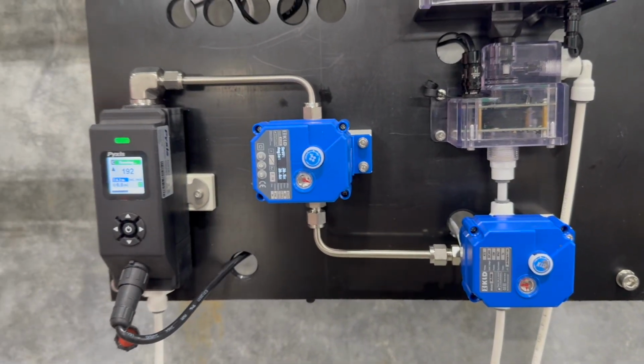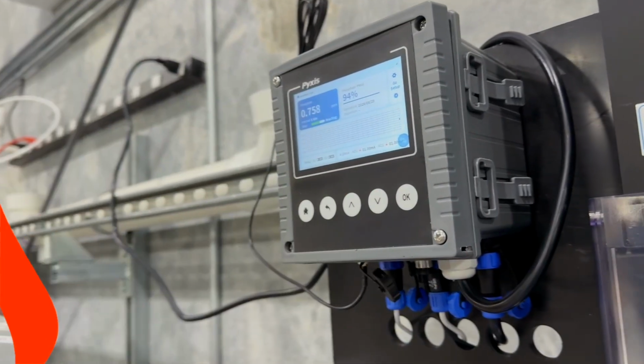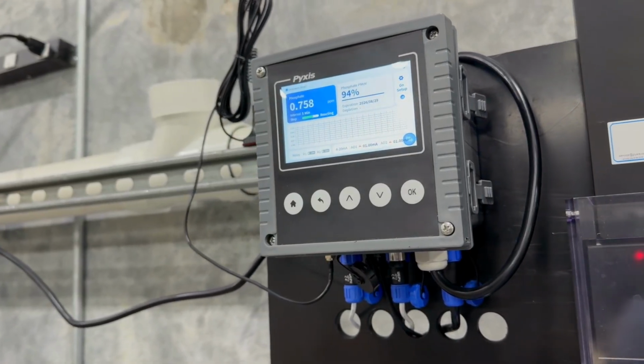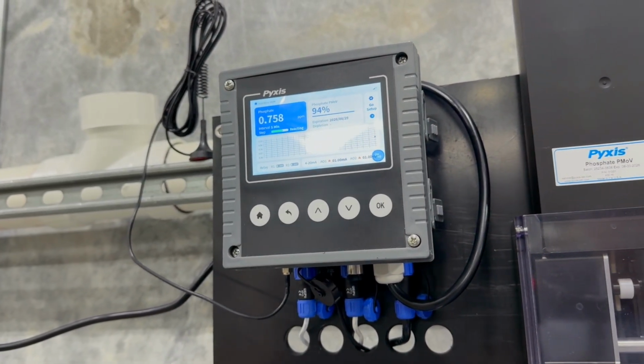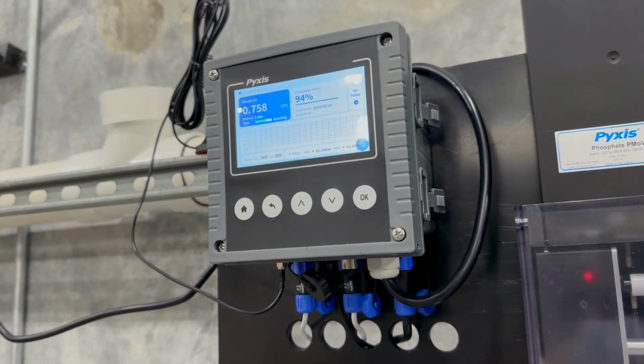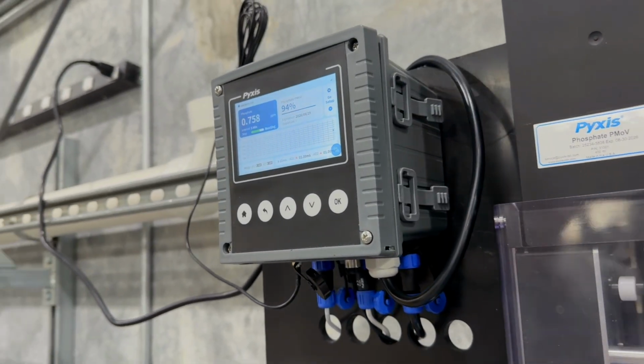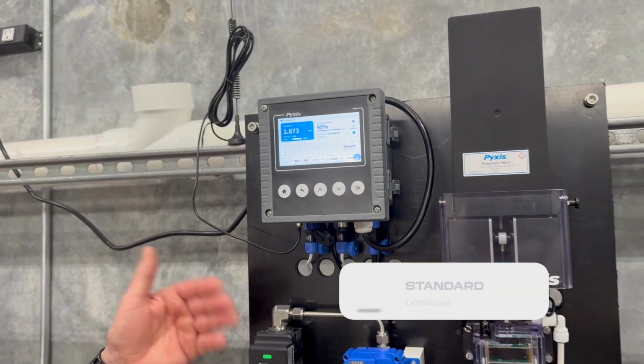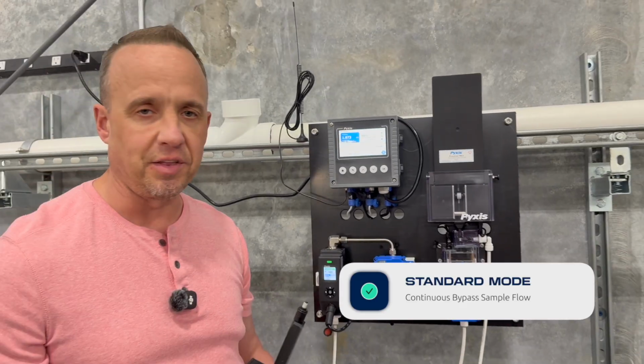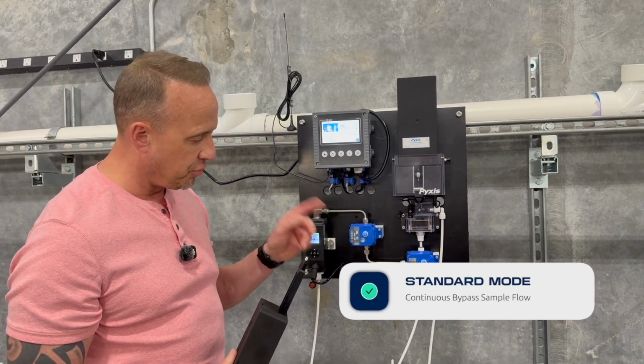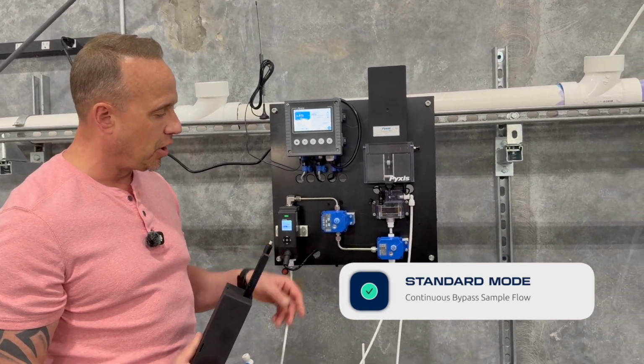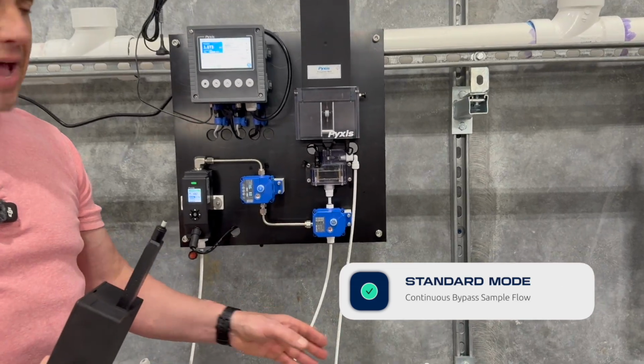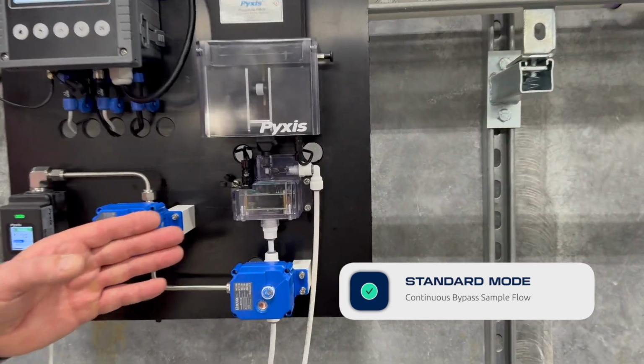times. The actual HMI of the analyzer has the capability of allowing the user to run the unit in both standard mode and what we call water savings mode. In standard mode, the operation enables bypass sample flow 100% of the time. So the sample will go through the flow meter, regulate the sample flow, and it will go to drain as it's waiting for the next sample iteration.